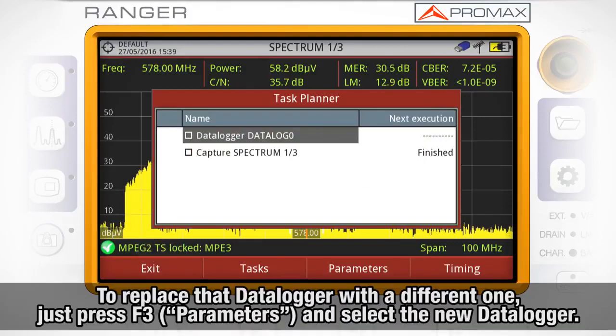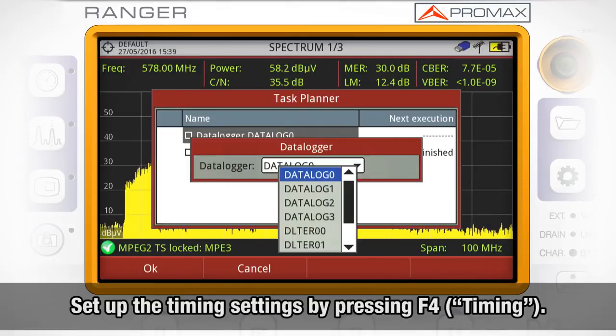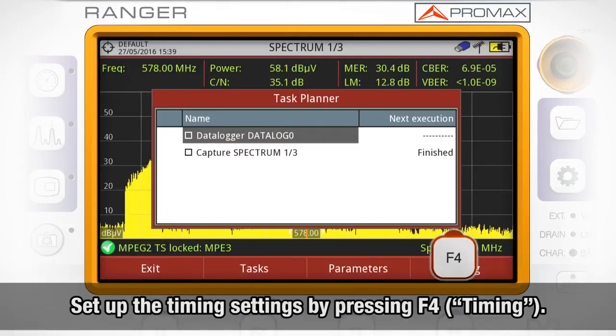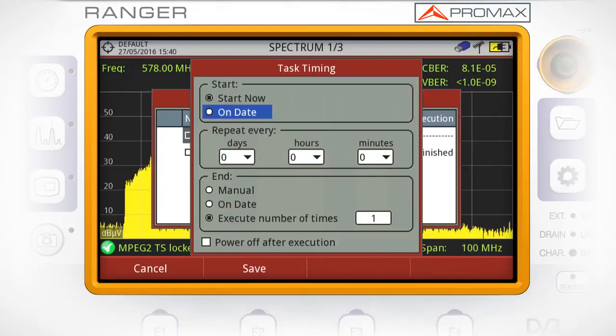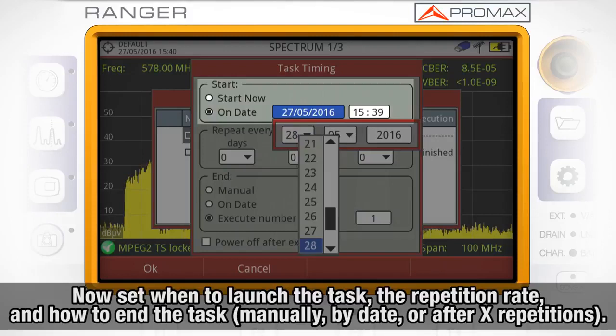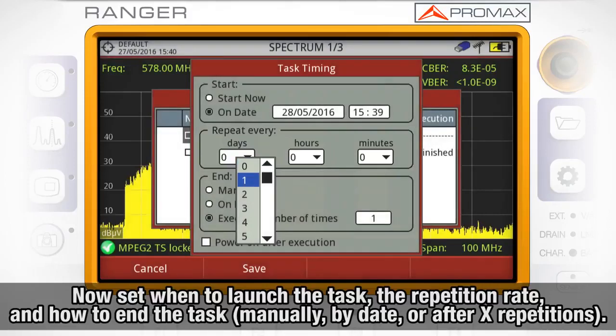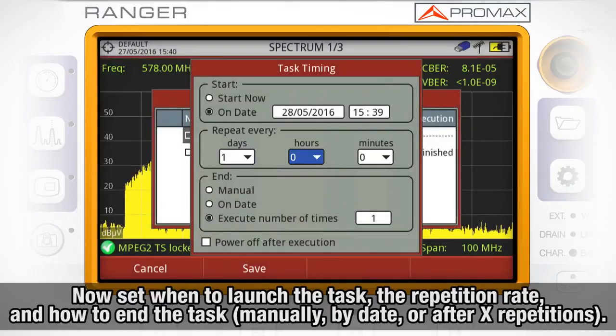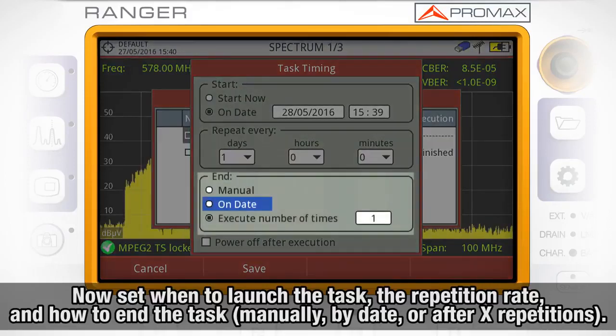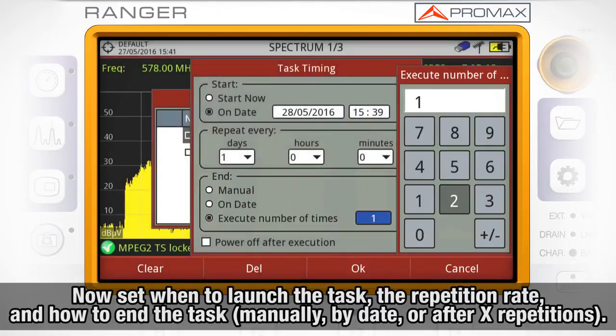In case we wanted to replace that data logger with a different one, we just need to press F3 Parameters and select the new data logger. If we press F4 Timing, we will open the timing settings. Here we inform the meter when to launch the task, the task repetition rate, and how to end the task — manually, on a specific date, or after a number of repetitions.